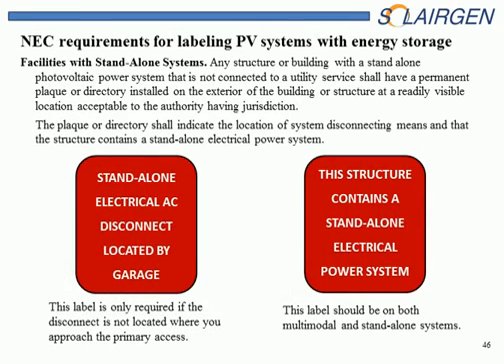The NEC requires for standalone systems on structures that there be these two labels, or at least one of them. The label on the right is required, period. "This structure contains a standalone electrical power system." The one on the left is only required if there's not an AC disconnect out there that's obvious. So when you approach a structure, you either see the label telling you where this AC disconnect is, or you see the AC disconnect, one of the two. So I think most off-grid systems will comply with this. Some little backwoods cabin may not, but if it's a home that's off-grid, I think you'll probably see this most of the time.